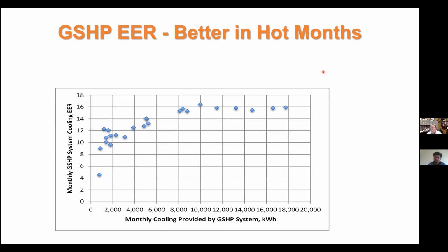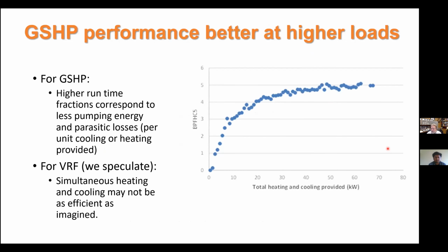In general, we found that the performance went up when the load got higher. Earlier, we plotted the EER versus the total monthly cooling provided. You can see in general, the months where we have more cooling, we get a higher efficiency. Same thing if we bin the analysis. I did this, I think, last year. I plotted the performance factor, which is the total heating and cooling provided divided by the total electricity. So we blended the heating and cooling together, and plotted that against the total heating and cooling provided. You can see the performance factor just goes up.